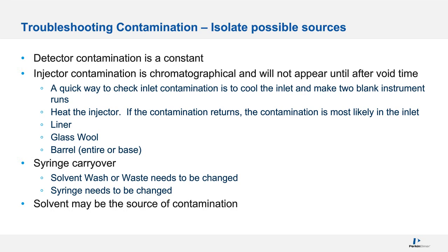The way I check my injector to see if it's the injector, I cool my injector, make 2 injections. Then I heat the injector up, make another injection. If it came back, then I know it's in my injector port. Solvents: for an instrument blank, just set up an acquisition, hit the run button on the GC. If the contamination goes away, it's not an instrument problem. I've had solvents be bad.